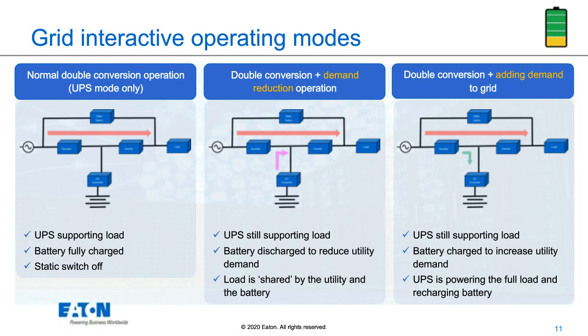On the far left, we see normal double conversion operation. Power comes in from the utility company and hits the rectifier part of the UPS, where it's converted from AC to DC. Part of that DC goes to charge the battery or keep it topped off if it's already charged. Then the inverter takes DC and builds a new AC output 24/7, 365, sending it on to the critical loads.